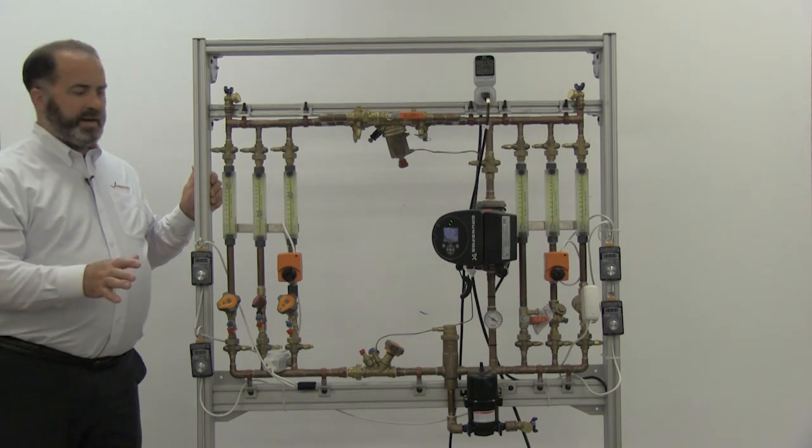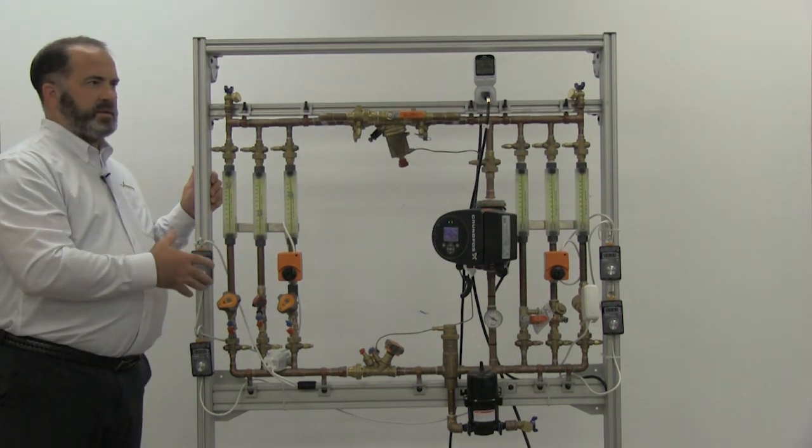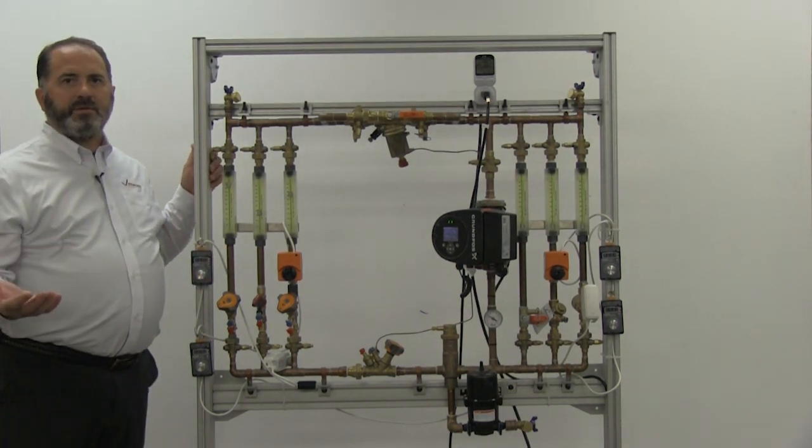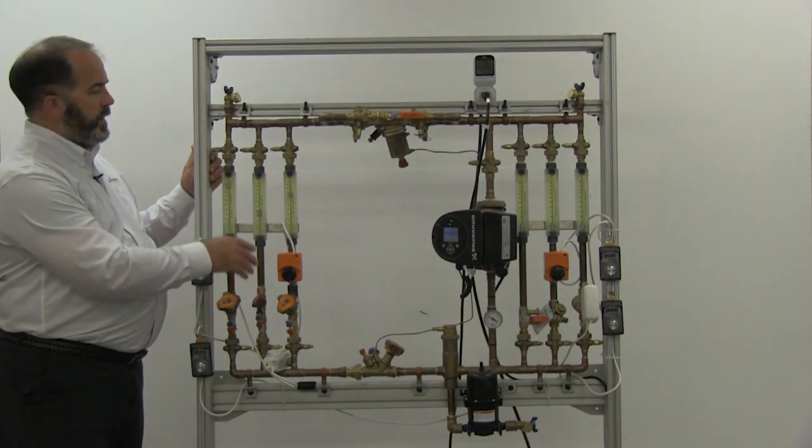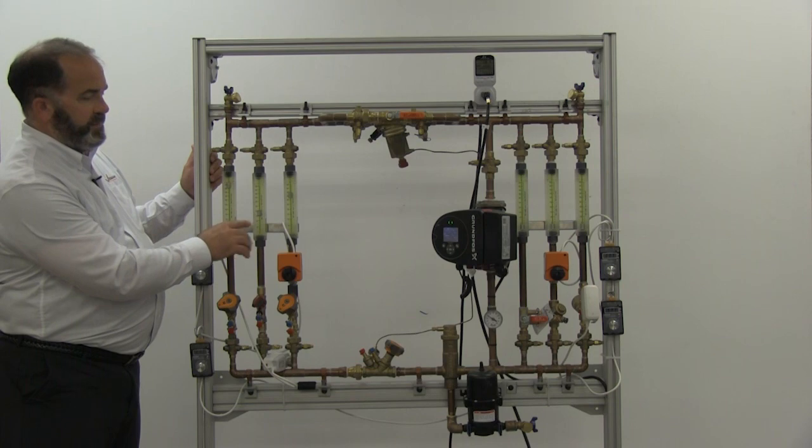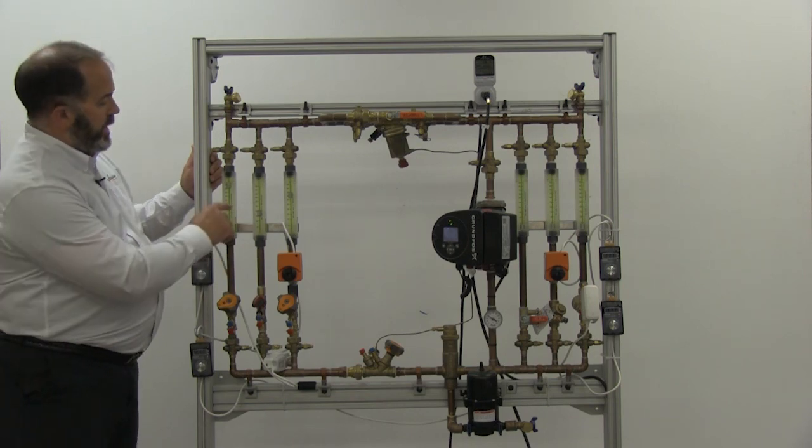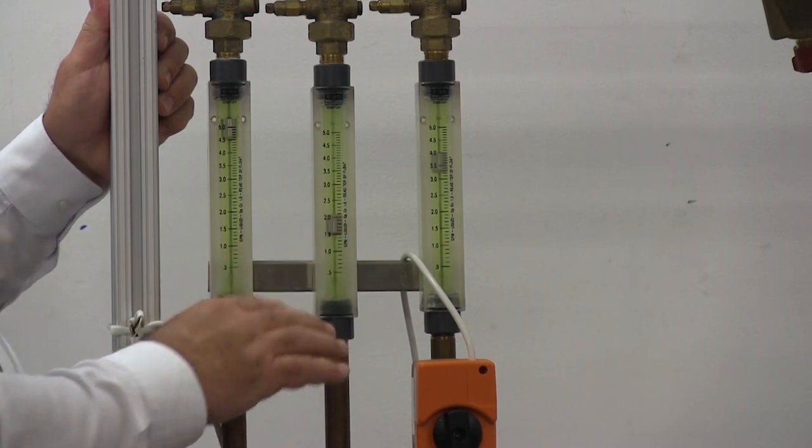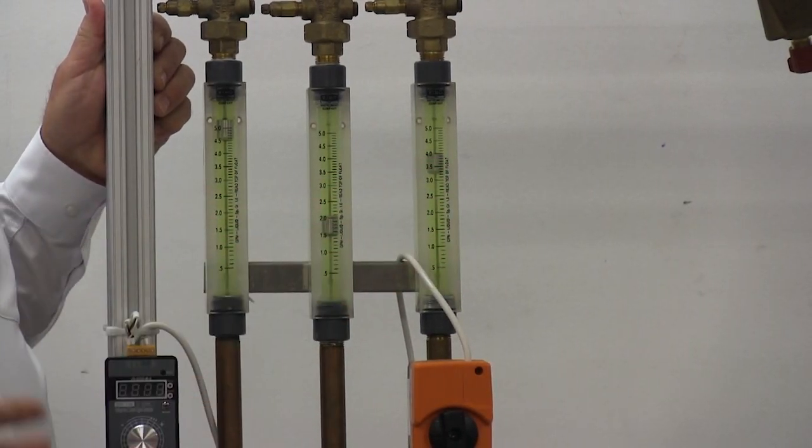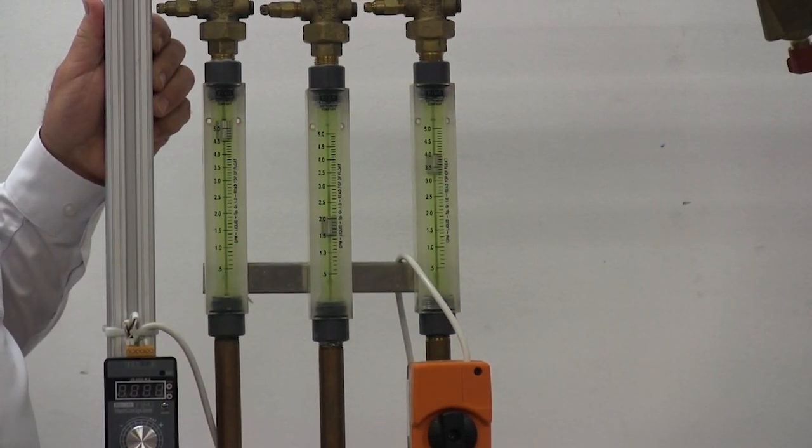Right now, the way my system is set up, I have basically an unbalanced system. This will simulate not having any balancing valves at all. So I have all these open as wide as they can go, and even though I have a design flow of 2 GPM, you can see that I have everything pretty well overflowing. This one is overflowing by about 20 percent, and the rest are overflowing by more than 100 percent.